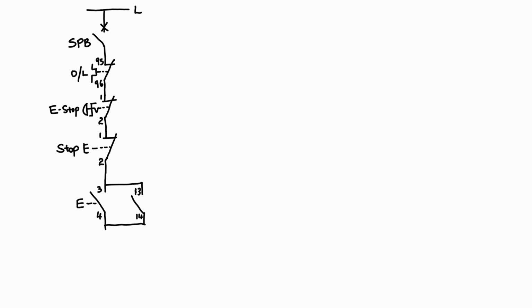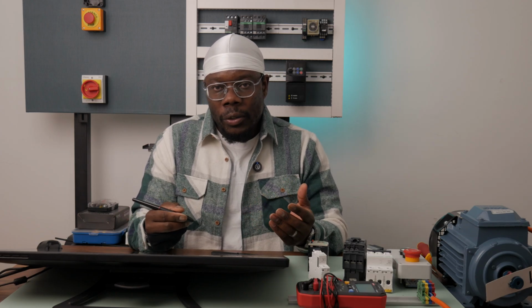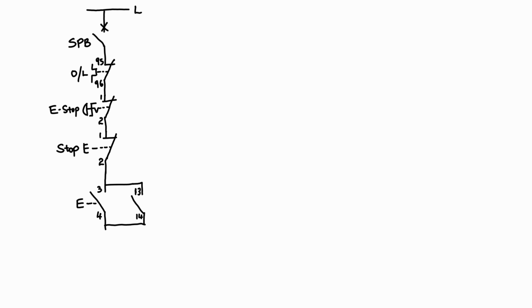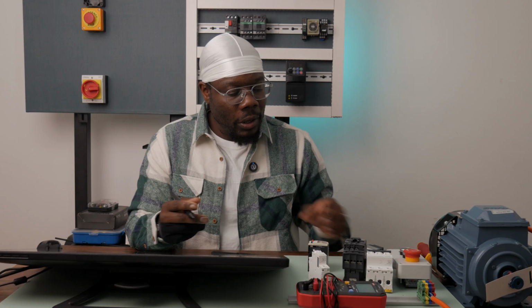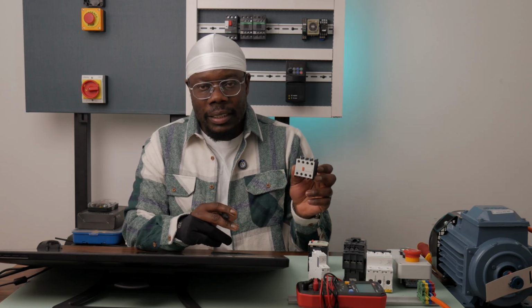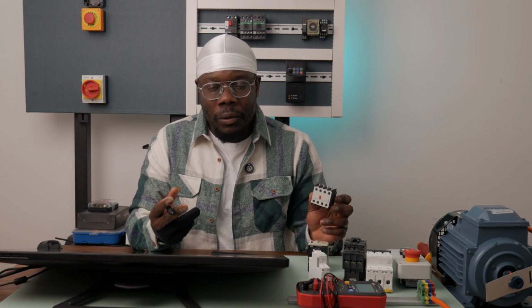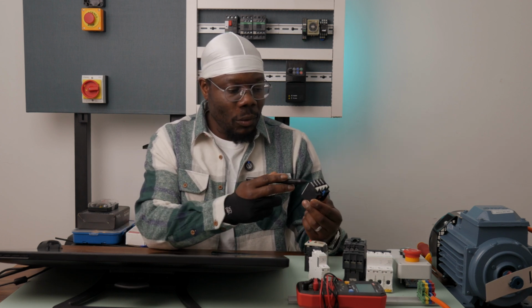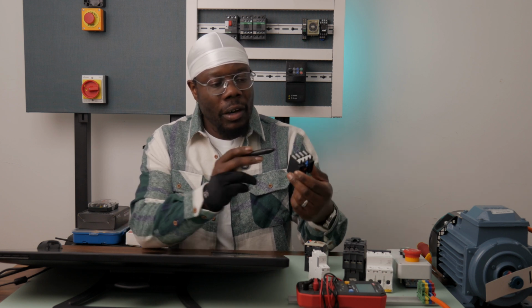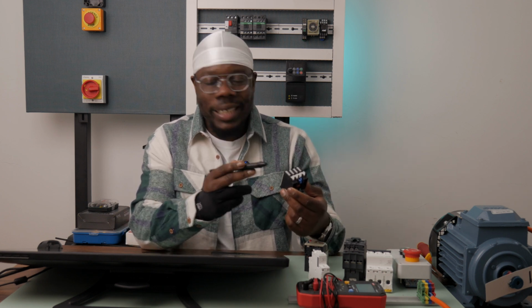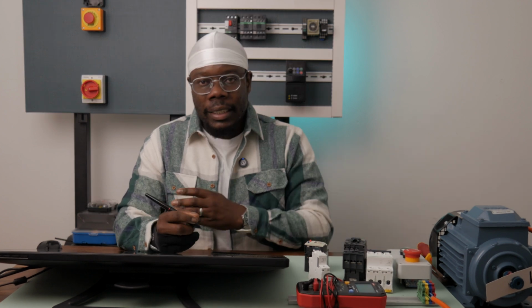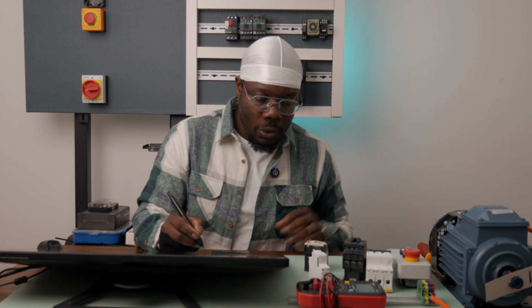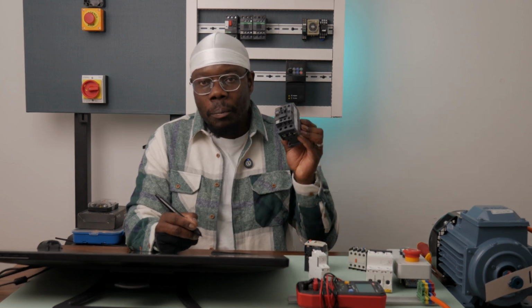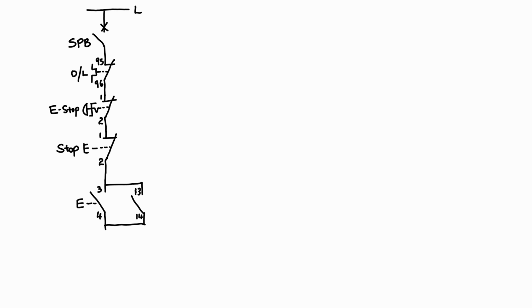Now the start push button is connected in parallel with your auxiliary hold in, and our auxiliary hold in is labeled 13 and 14. But we shouldn't be memorizing those numbers. What we should just know is it should be a normally open contact. If we are using this auxiliary contact block, there's no 13 and 14, but can we say we don't have a normally open contact? Of course, we have one. If you're going to be using this auxiliary contact block, you're going to be utilizing 53 and 54 or 83 and 84, as long as the least significant numbers are 3 and 4. So we're going to be using the auxiliary contacts that are built onto this contactor. So they are labeled 13 and 14.